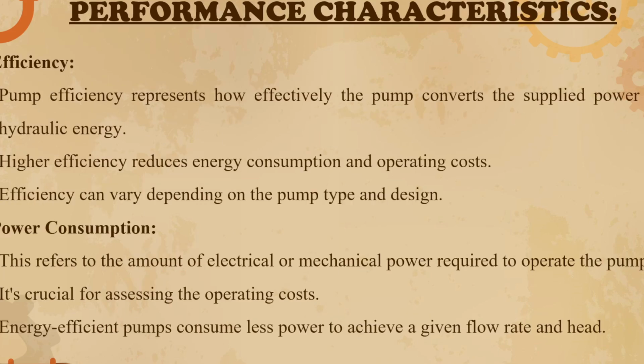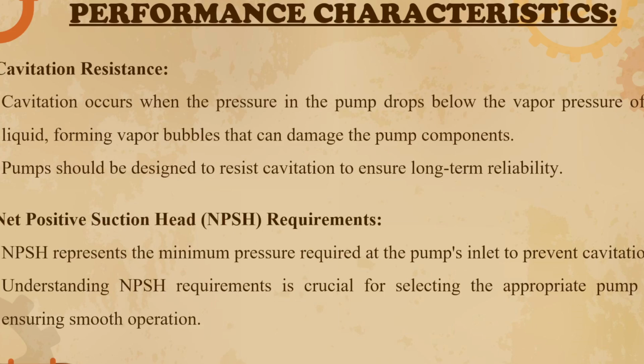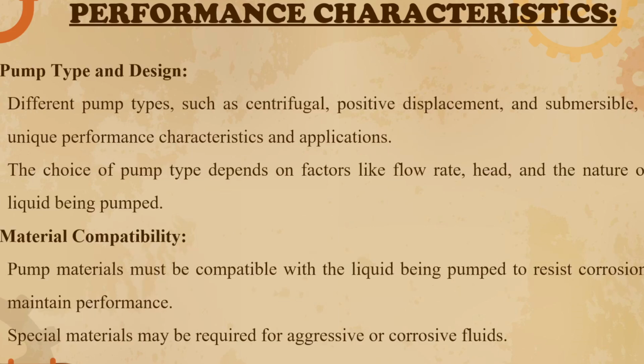So third is efficiency, fourth is power consumption, fifth is cavitation resistance. It occurs when the pressure in the pump drops below the vapor pressure of the liquid, forming vapor bubbles that can damage the pump components. Therefore, pumps should be designed to resist cavitation to ensure long-term reliability. Another characteristic is the net positive suction head, or NPSH, requirement. NPSH represents the minimum pressure required at the pump's inlet to prevent cavitation. It is crucial for selecting the appropriate pump and ensuring smooth operation.